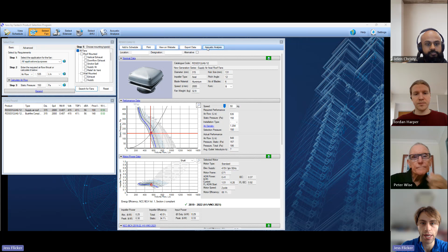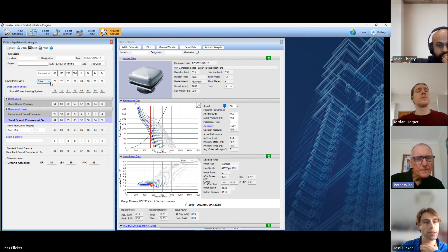So you can specify whether that's at the inlet or the outlet of the fan. In this case, it's inlet because of the type of fan it is. Well, actually, hang on - if you're analysing the noise downstream of the fan, you probably need to look at the outlet. But this is a suction - it would be at the inlet in this case, right? Because it's roof mounted - is it supply or exhaust? It's a supply fan, outside air supply. Yeah, right, so then you would do outlet. So it's probably not much different, but there may be a difference of 1 dB or something like that.